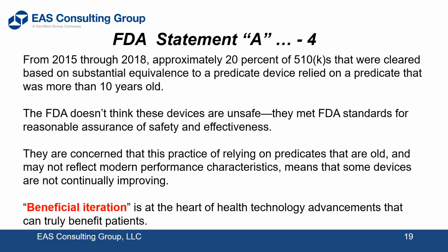I'm not going to go into a lot of detail on these points right here. You notice here from 2015 to 2018, approximately 20% of the 510Ks that were cleared were based on substantial equivalence to a predicate device that was more than 10 years old. Well, that doesn't do any good for the field. Basically, you're just doing a me too. And they'd like to see you go a little bit beyond the me too without getting so far advanced that you're stuck going to a PMA route.